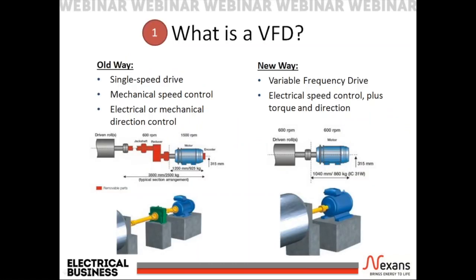Traditionally, motors were single-speed, either on or off. To change the direction or speed of the motor, a mechanical system such as a gearbox or a contactor would have to be used. This adds mechanical components that require physical space and regular scheduled maintenance. A VFD allows the direction, speed, and torque of the motor to be precisely controlled with a very simple mechanical system. The physical space requirements are much smaller, and the need for regular scheduled maintenance is at a minimum.